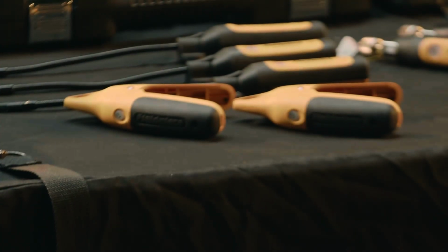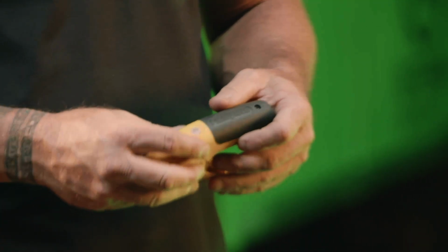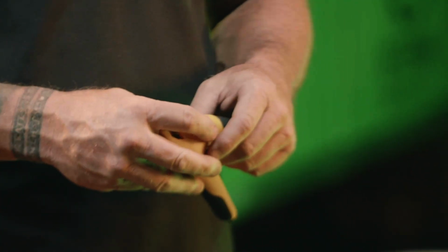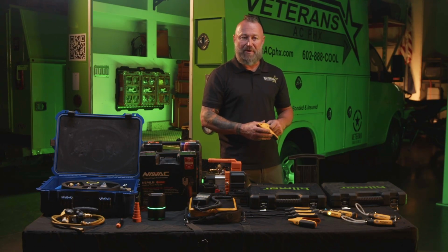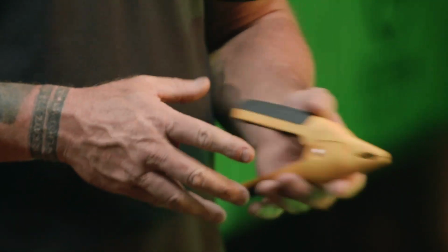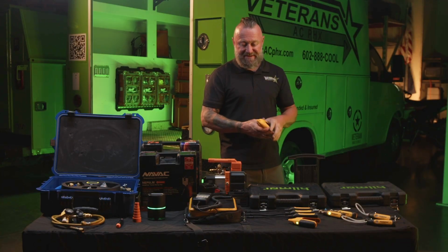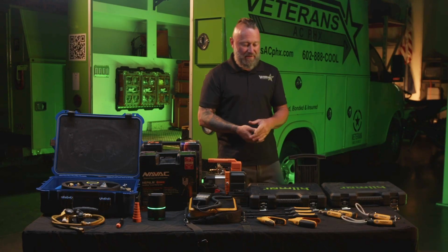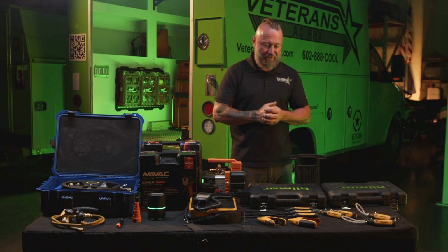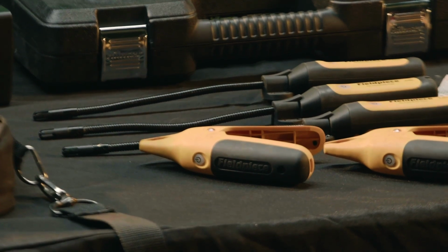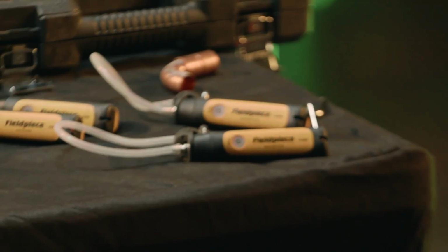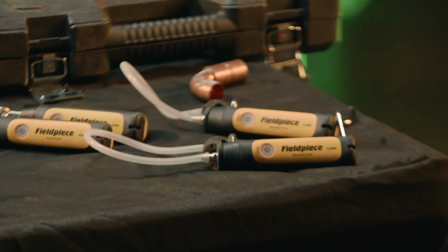Pipe clamps here, these are going to go on the outdoor unit. One's going to go on the suction line, which is your larger line, and the other one's going to go on your liquid line, which is a smaller line, and sometimes it's going to go on the discharge line. Generally, what we like to see on the suction line is 42 to 52 degrees. I'm going to come in, generally hook up my pressure gauges first, and then we'll come back out, put the clamps on, and then we'll get into drilling the ductwork for our manometers to check static pressure.